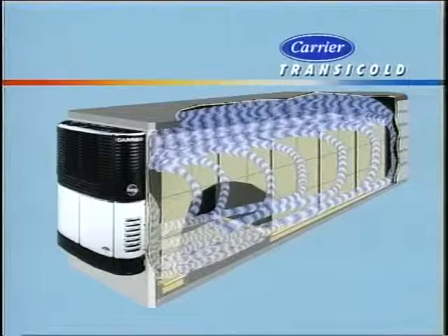to status OK. The defrost cycle will last from 5 to 20 minutes, depending on how much ice is on the evaporator coil. The unit should be manually defrosted once a day, and more frequently when the trailer is loaded with a warm, moist product such as fresh produce. Manually defrost the unit right after loading is complete, and again later if the box temperature is not coming down to set point as quickly as usual.